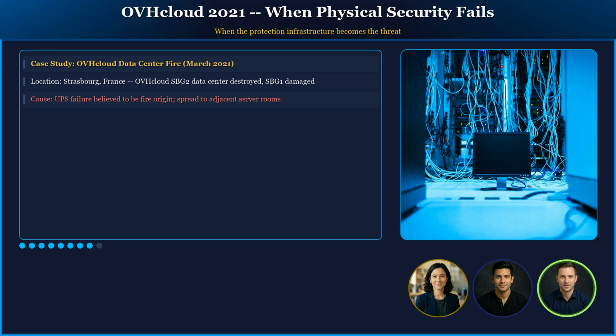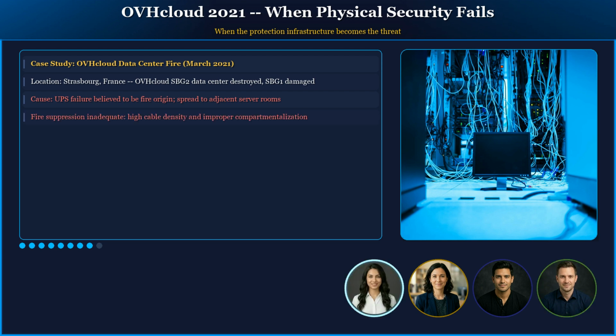Server rooms contain enormous amounts of combustible material: plastic-jacketed cables, foam packaging, cardboard. The suppression system must be designed for the actual thermal load, not just rated for the floor area. The customer impact was compounded by backup strategy. OVH Cloud offered backup services, but backups stored in the same data center were destroyed with the primary data. Customers who assumed geographic diversity of their backups did not have it. Off-site backup storage is not optional for availability.